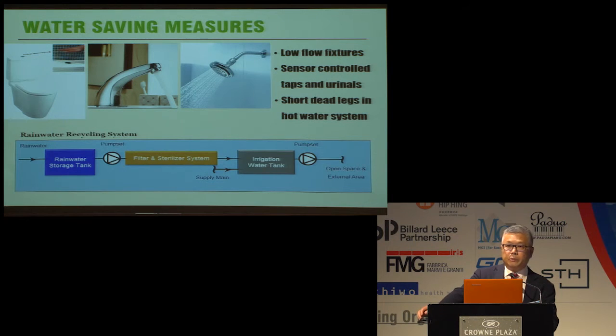Hospitals consume a huge amount of water. To reduce water consumption, we can use low-flow fixtures for sinks and showers, sensor control taps, and urinals, and then dual flush WCs. Minimizing dead legs in the hot water recirculation loop can also reduce the time for the hot water to reach the tap, and also reduce the risk of Legionnaires' disease, as Dr. Long mentioned earlier on. Rainwater could be harvested for irrigation of soft landscape to reduce the use of fresh water.